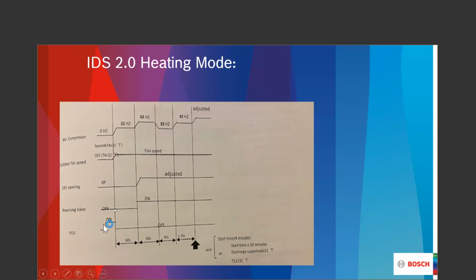We chose to do that because the reversing valve is energized by the 24 volts, but it does not get switched or moved by just the 24 volts. It gets moved by the pressure differential inside the pilot tubes on each side of the valve itself, and it goes from a high pressure situation over to a low pressure situation. So here we are, we're running for 1 minute, and we're going to then bring on the reversing valve. And when we bring on the reversing valve, now we're in the heat mode.